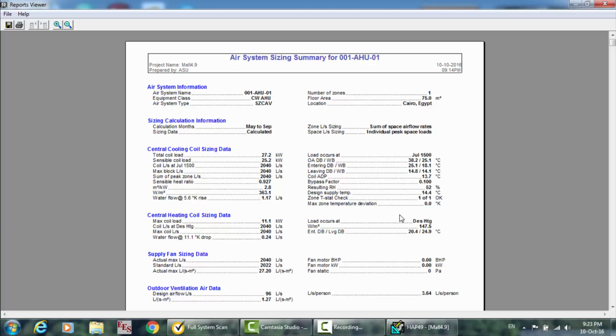Okay, but if the calculations were impossible and HAP did not get the throttling range, it will tell you 0 of the number of zones here. If we have 3 zones, it will be shown here 0 of the 3 zones, or 1 of the 3 zones, to get it. Here the throttling range is good. Okay, no problem. But you may find this is red. Okay, this means that HAP did the calculations and found that it is impossible to get the required temperature inside the room. It will not be 24 or 25. No, it will be more than this, according to the psychrometric calculations.